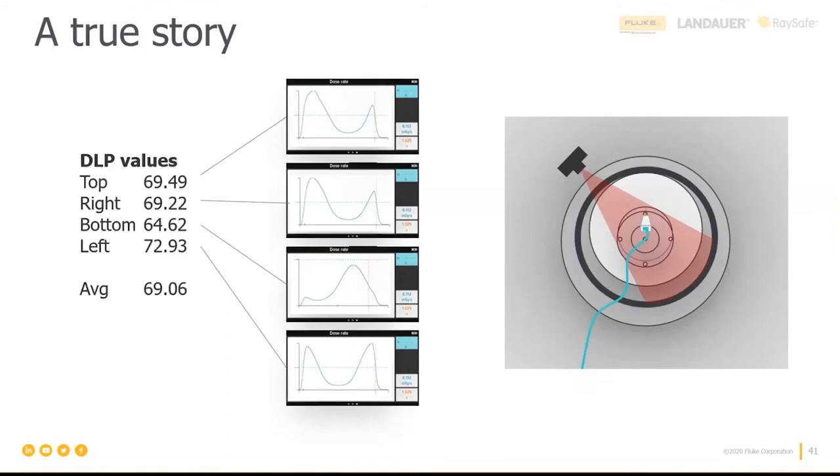On the other hand, the reason for averaging the four peripheral holes is the uncertainty of this measurement. So when you can figure out that you're accurate in your estimation of the dose, it might be enough to only measure one peripheral hole. It depends on how the couch interferes with your measurements. But this way, you don't have to do like this company did, five measurements and taking the lowest one. You can figure out from the waveform which value you can trust.